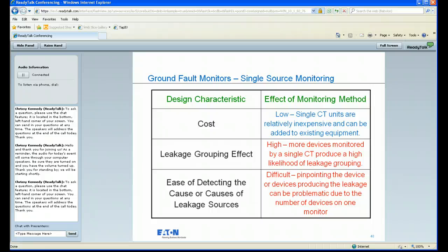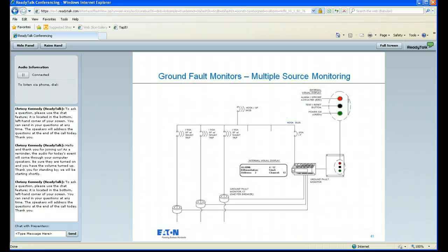From a cost standpoint, the single source monitoring device is relatively inexpensive. You're providing a single CT around usually the main circuit breaker or main lines coming into a piece of equipment. Leakage grouping can be a cause of concern for this device because as many boats or vessels as are being powered by that single circuit breaker or piece of equipment are judged as a collective group rather than on an individual level. That also makes pinpointing the cause or causes of the leakage very difficult because again, you're going to have a good number of vessels being monitored by that one device.